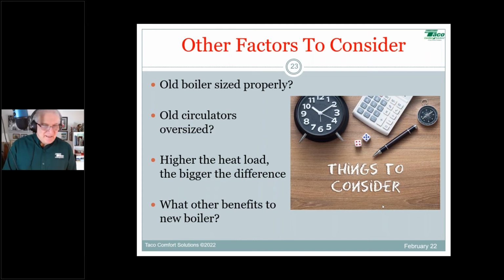That's pretty cool. Did you discuss outdoor reset and how it affects efficiency? Very obliquely, I hope we got that. Outdoor reset means the warmer it gets outside, the lower temperature the boiler makes. You select different parameters, and a lot of these boilers now have intelligence inside that helps make it as efficient as possible. Compare outdoor reset with turndown ratios and you really start to maximize overall boiler efficiency. The ratio I keep in my head is, for every 3 degrees you lower water temperature, you cut fuel consumption by 1%.